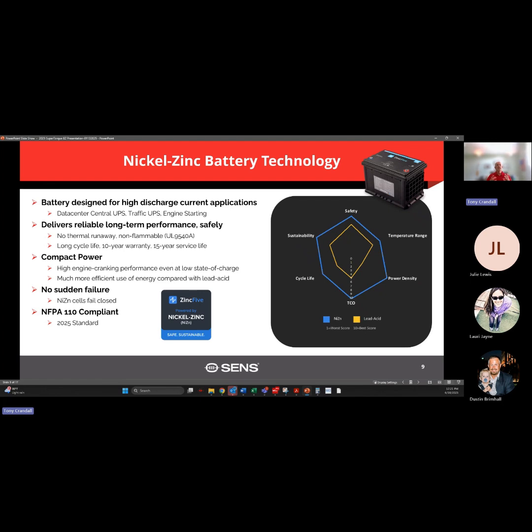So, no sudden failure. The nickel-zinc chemistry itself does not experience sudden failure. If and when the battery does fail, it actually fails in a closed or conductive state, meaning that one last time that battery or generator is going to be needed to start, it will start the generator.